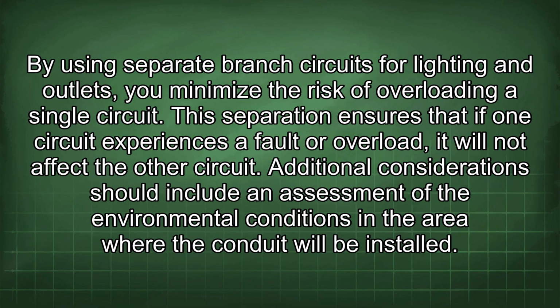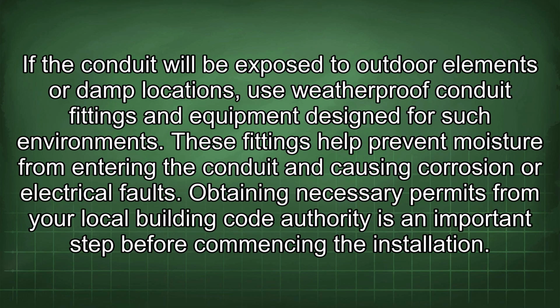Additional considerations should include an assessment of the environmental conditions in the area where the conduit will be installed. If the conduit will be exposed to outdoor elements or damp locations, use weatherproof conduit fittings and equipment designed for such environments. These fittings help prevent moisture from entering the conduit and causing corrosion or electrical faults.